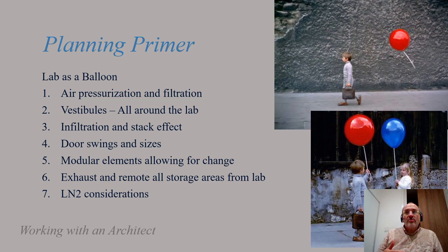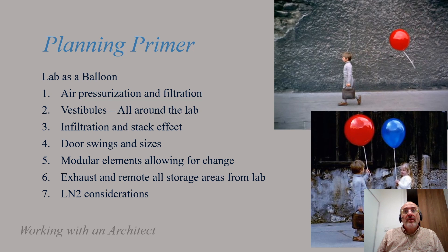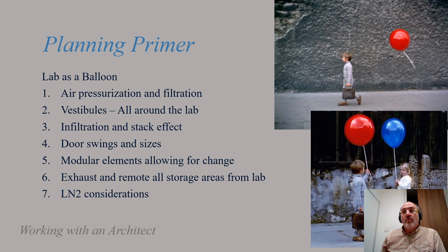Use modular elements as much as possible to allow for future change, particularly as automated procedures increasingly take over lab space. One key issue is making sure you exhaust all spaces around the laboratory that contain materials, and run a cycle that allows out-gassing in a heated environment over a week before materials are brought into the laboratory. Liquid nitrogen is one of the dirtiest elements — keeping it separate in its own space, tracking the LN2 flow, is a critical part of your planning.